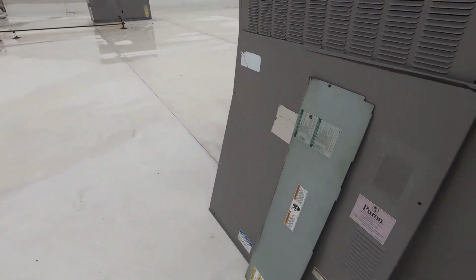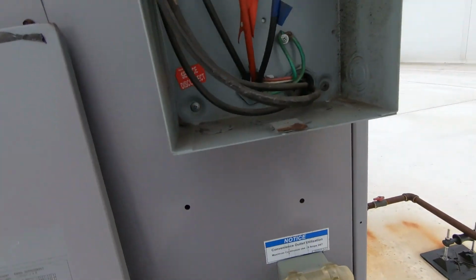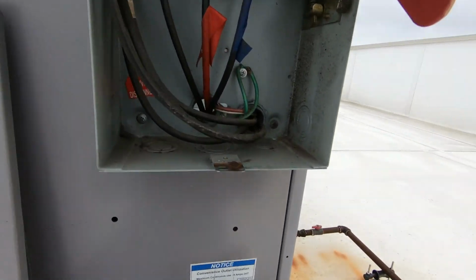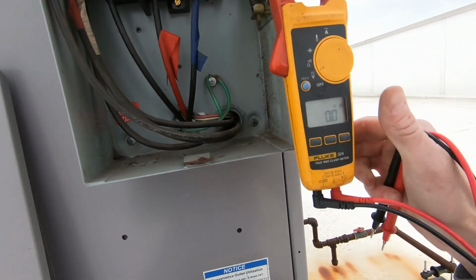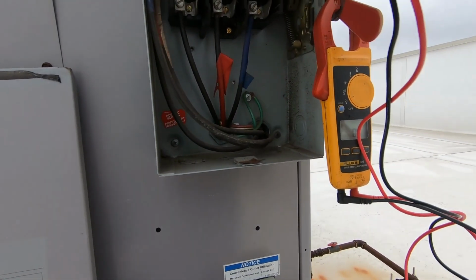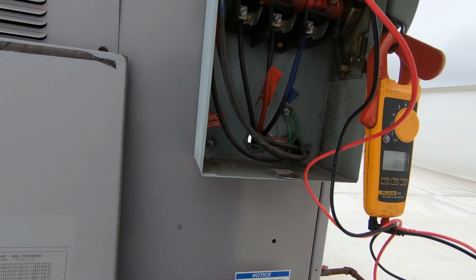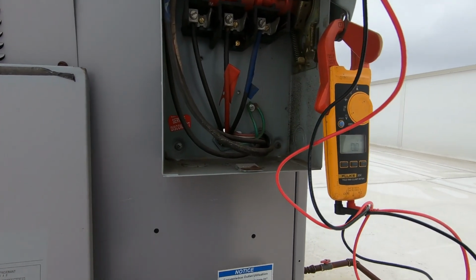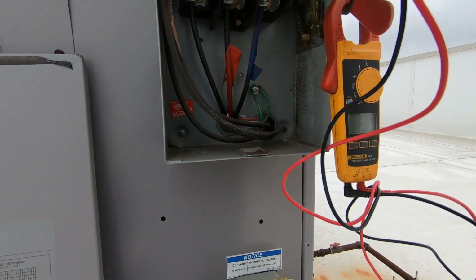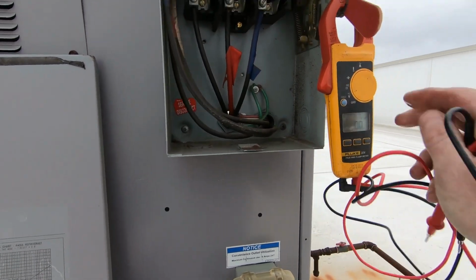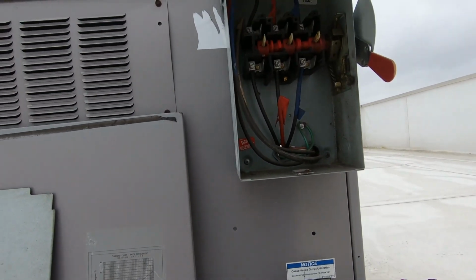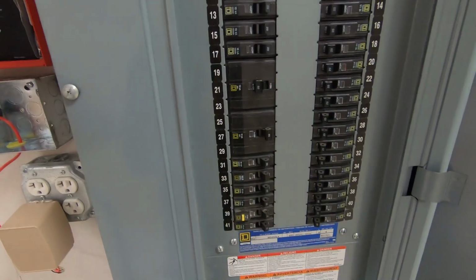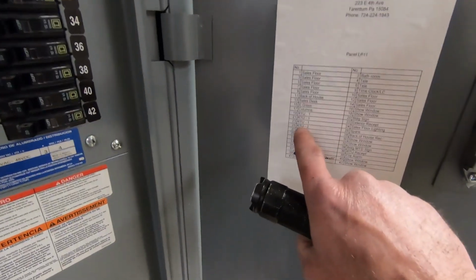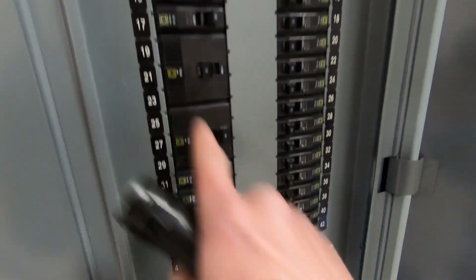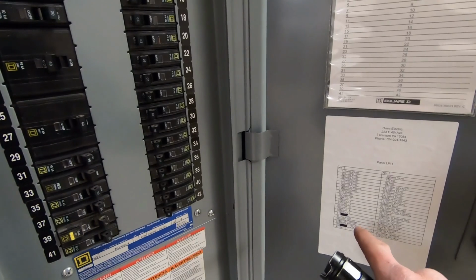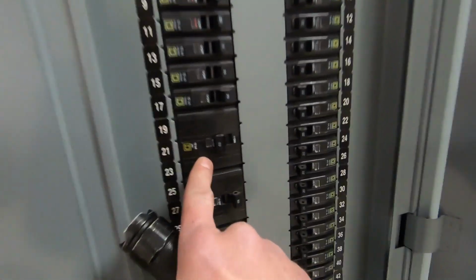I doubt it. I'm wondering if the fire department shut off the breaker, but they shut off the disconnect up here. Yeah, I got no power coming up from the breaker. All right, well, let's go find out why. All right, it's saying here RTU1 is off, but I think they're either mislabeled on the roof or in the panel because it's not tripped.